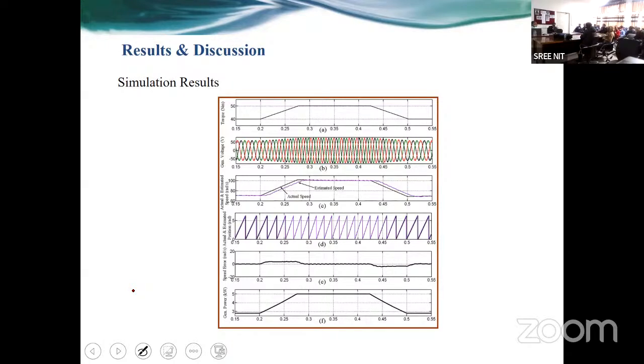As you said, in the wind DFIG, the induction generator, 30% of the power supply is fed from the rotor side to the grid, and 70% from the stator to the grid. Then why can't we transfer 100% from the stator to the grid? Why are we using 30%?